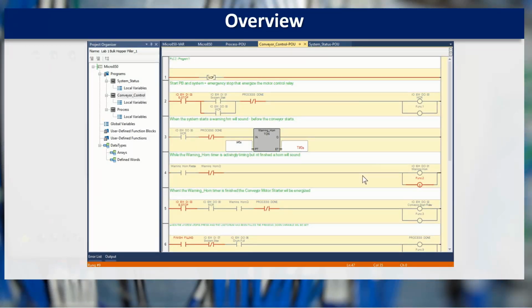And basically allowed the system to fill up the tank, and then in a blink of an eye everything gets reset. The conveyor stopped, and we have to start the system up as we did before. Same thing applies on the other part of the equation, because the other part of it was to ask that you stopped it on a full e-stop. So we start the whole system, I lose the e-stop, and it all shuts down.